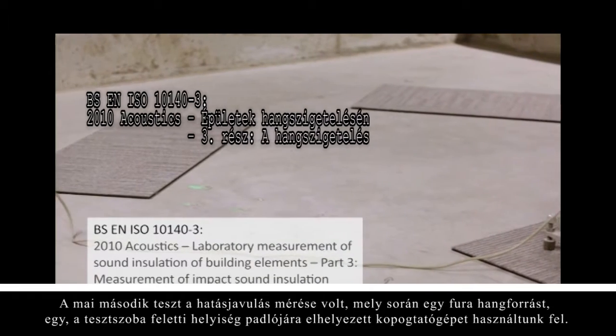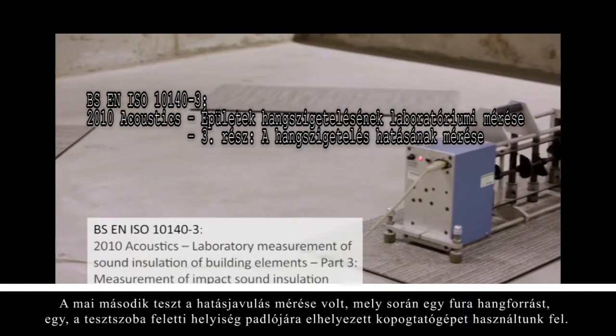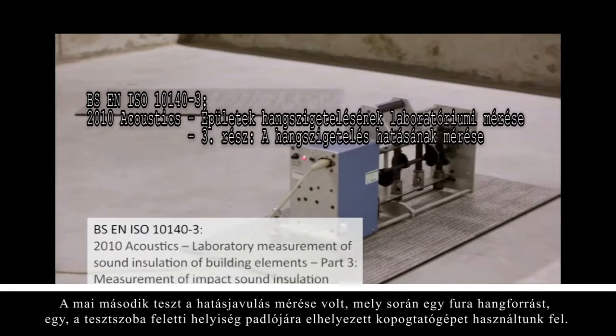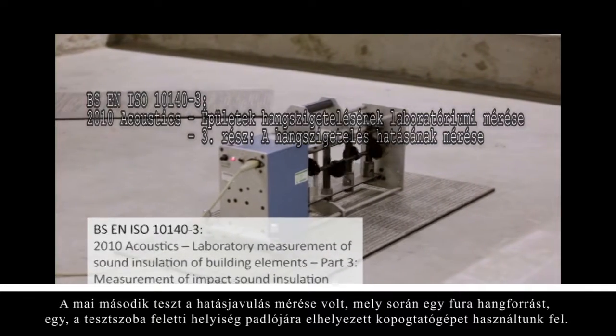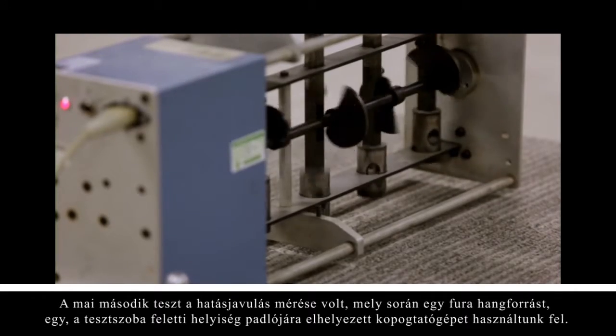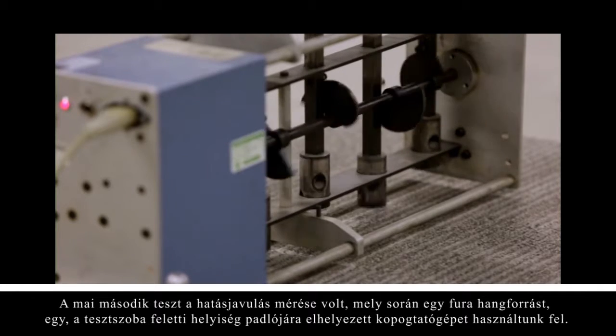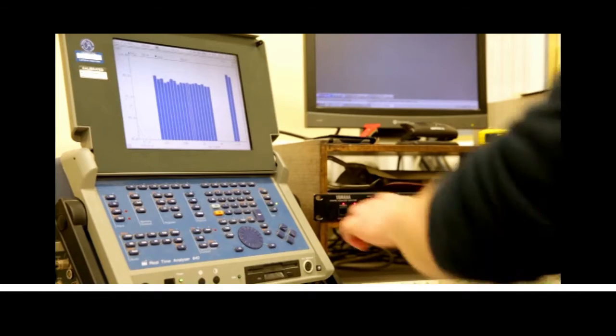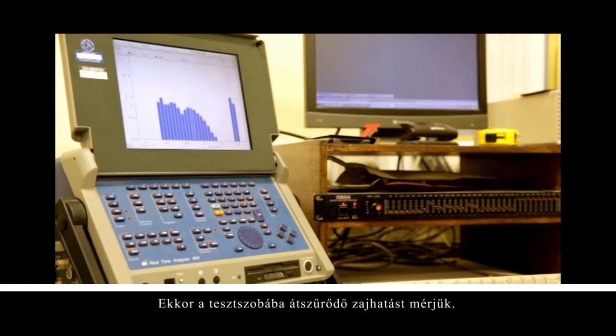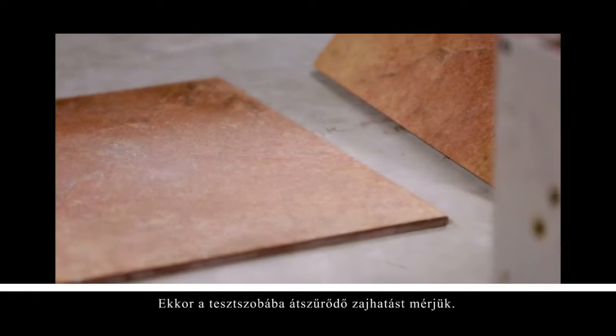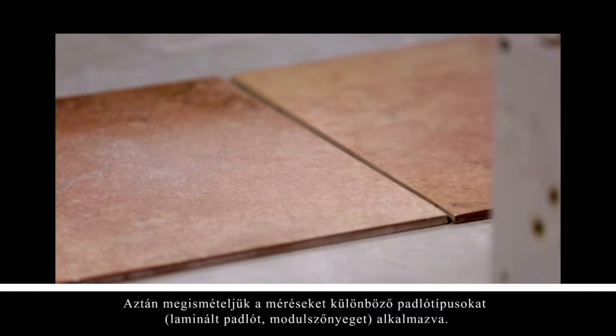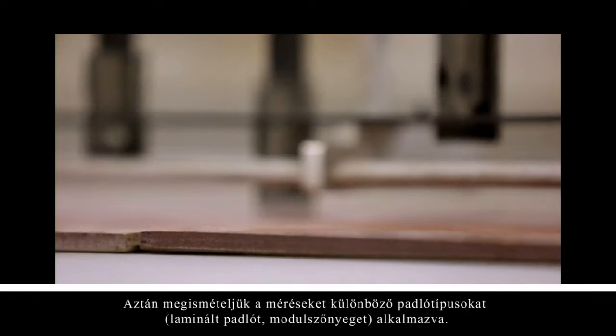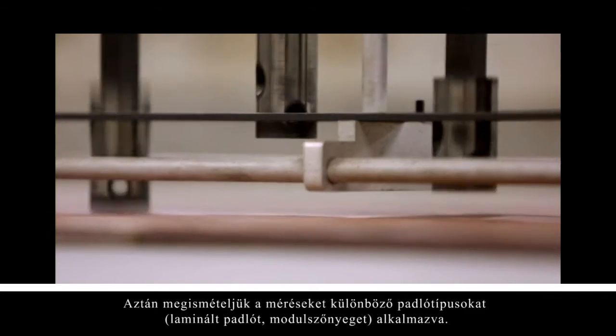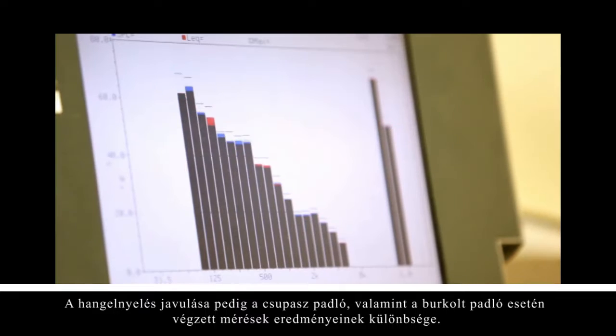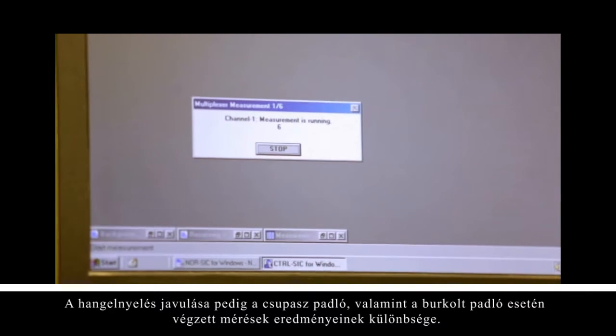The second test today was a measurement of impact improvement, which uses a known sound source, i.e. a tapping machine, that is placed on the floor above the receiving room. We'd measure the impact noise transmitted into the receiving room, and then we would repeat the measurements with some kind of floor covering, be it laminate flooring, carpet tiles. The impact improvement is the difference between the bare floor measurements and the sample on the floor.